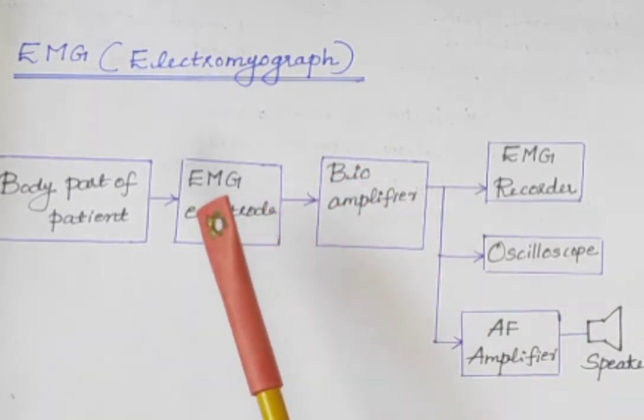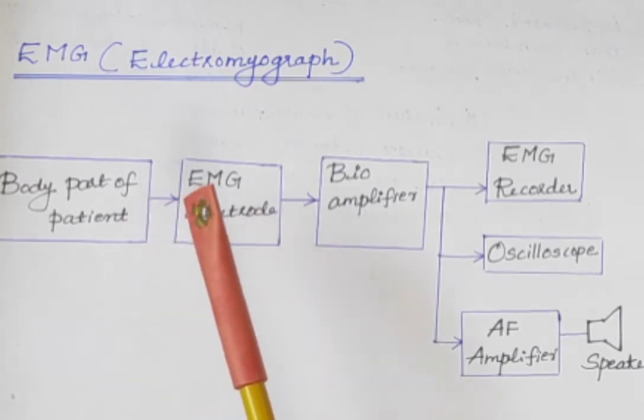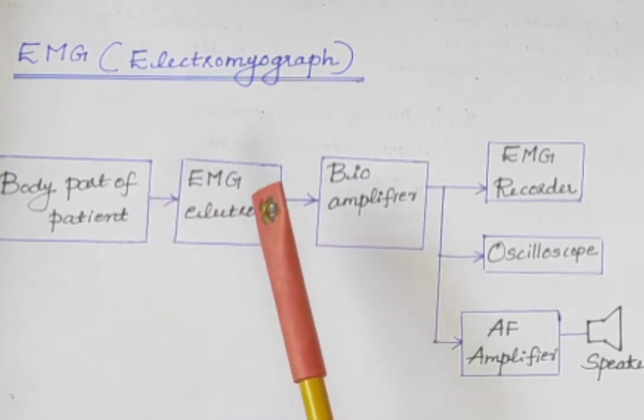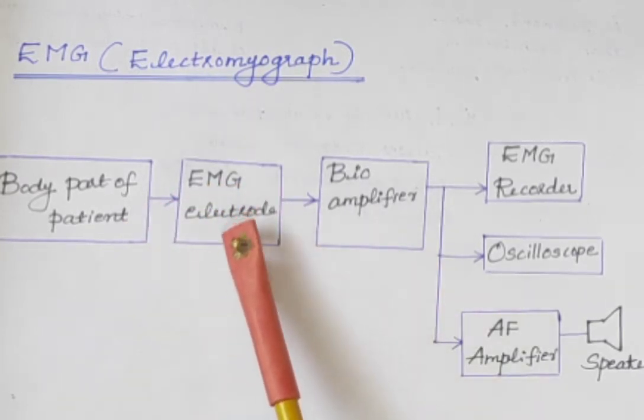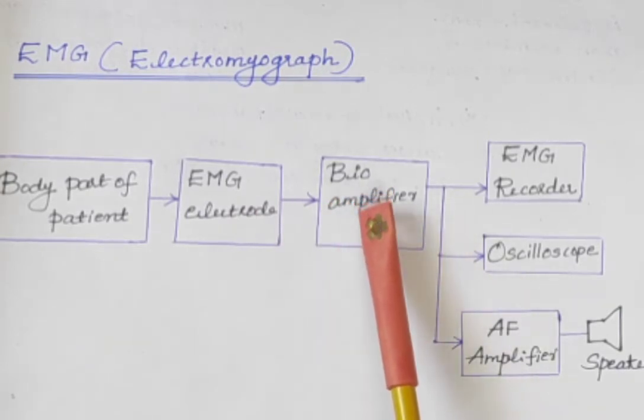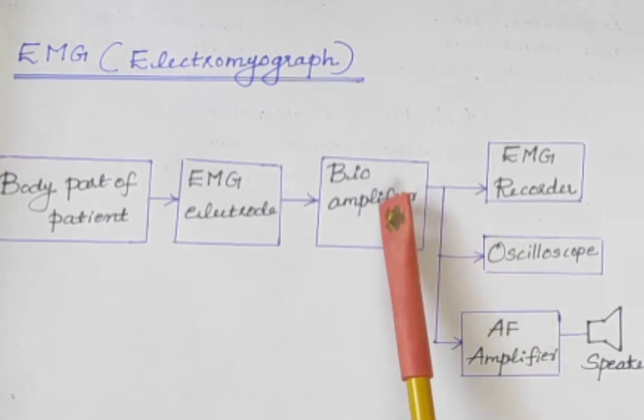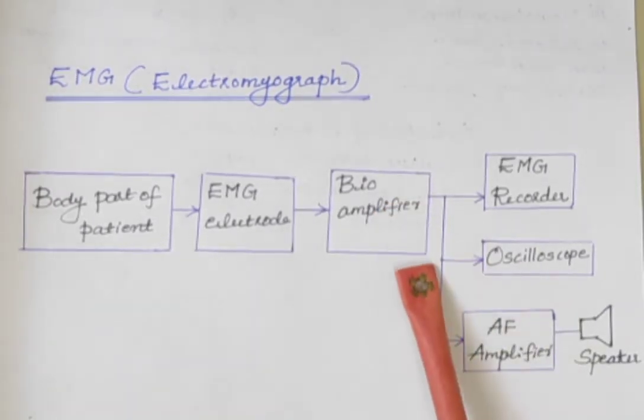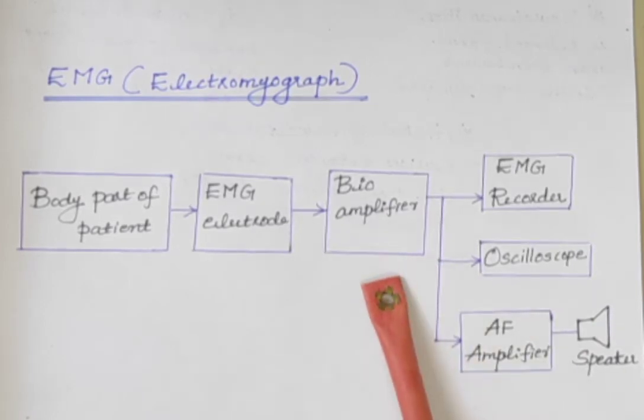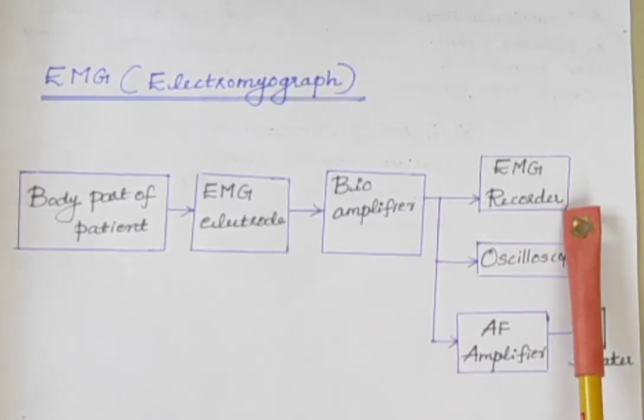EMG signals from the patient are measured using EMG electrodes and given to the bioamplifier. It is used to amplify bioelectric signals obtained from EMG electrodes. After amplification, EMG signals are given to EMG recorder.